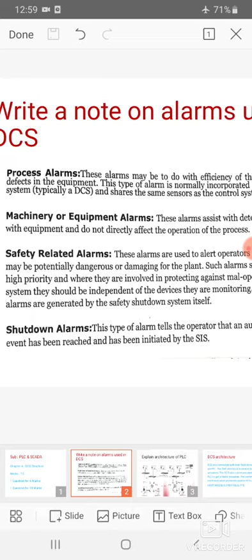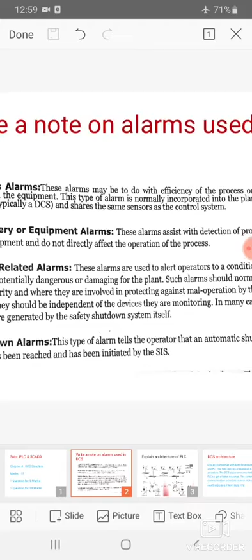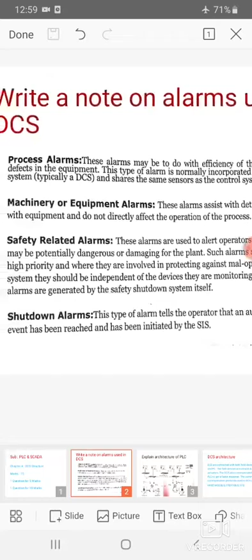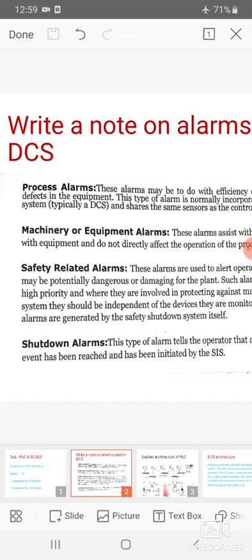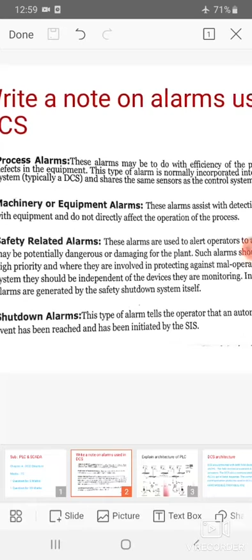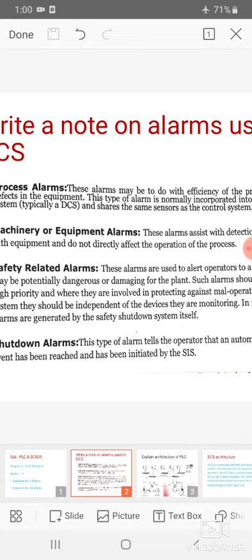Next, coming to the safety alarms, which are used to alert operators to a condition that may be potentially dangerous or damaging for the plant. Such alarms should normally have a high priority, and where they are involved in protecting against maloperation by the control system, they should be independent of the devices they are monitoring. In many cases, these alarms are generated by the safety shutdown system itself. The next is shutdown alarms. This type of alarm tells the operator that an automatic shutdown event has been reached and has been initiated by the SIS.